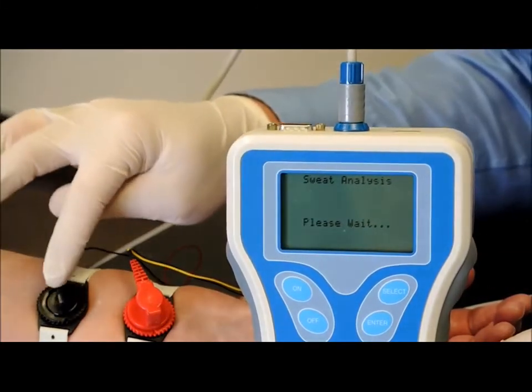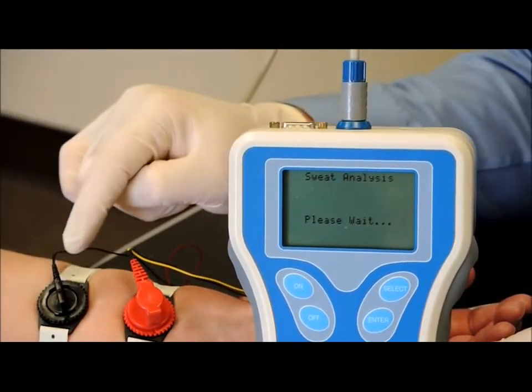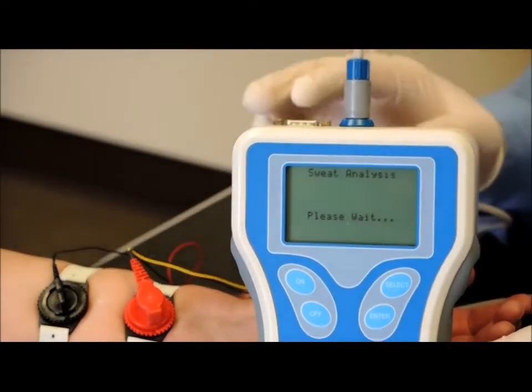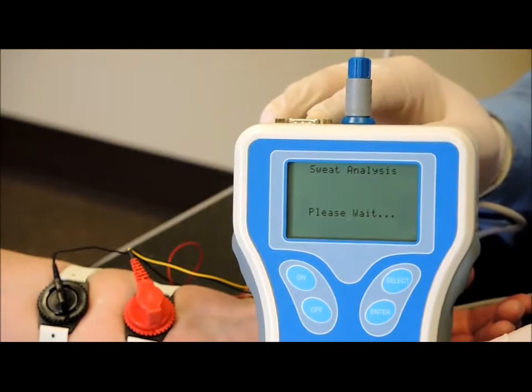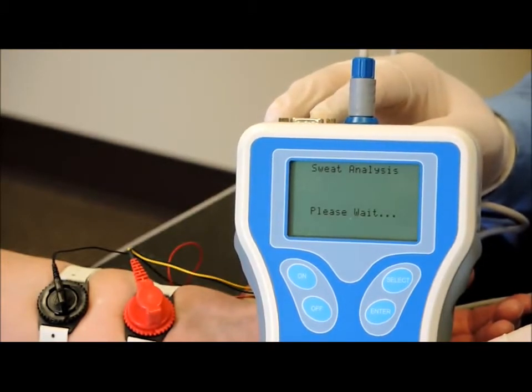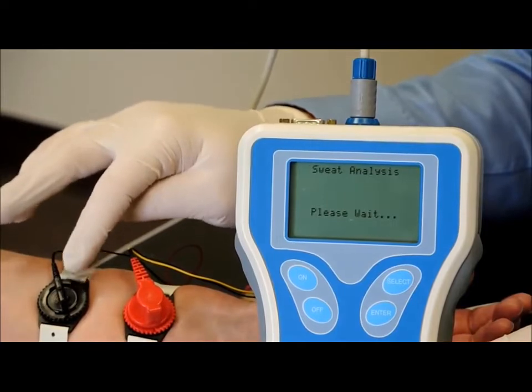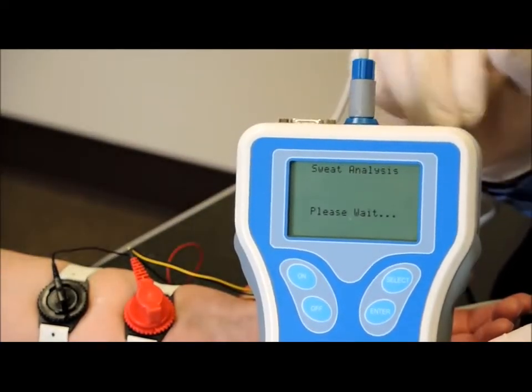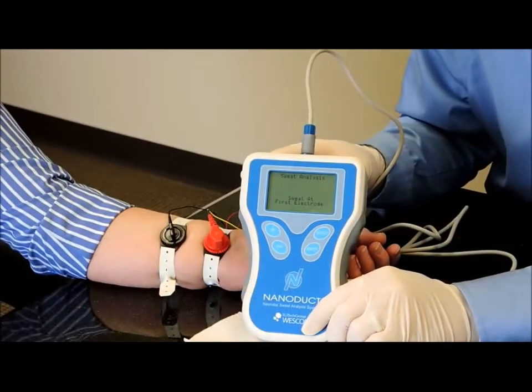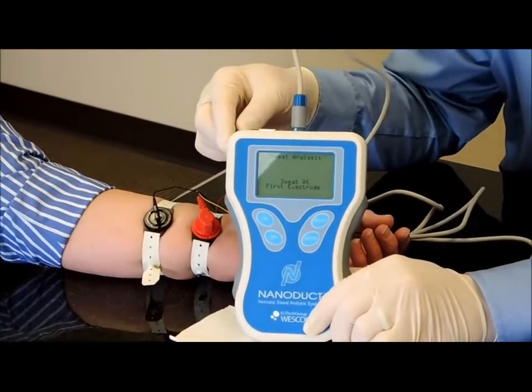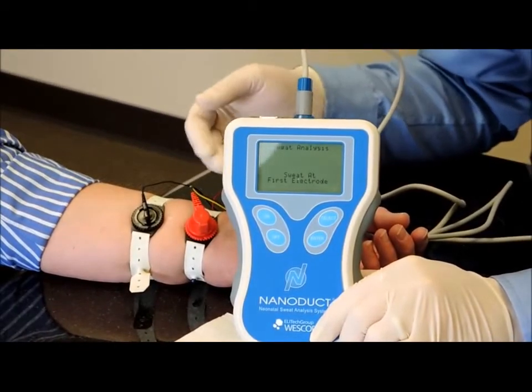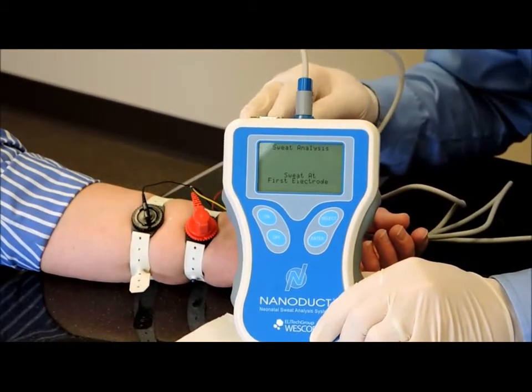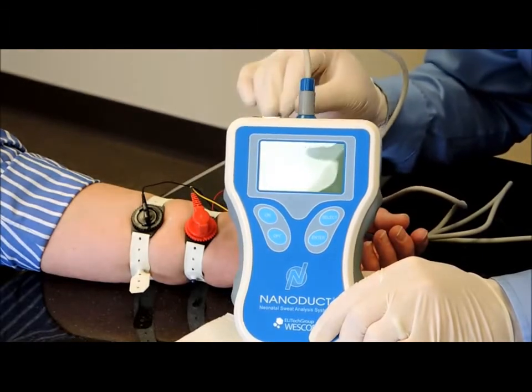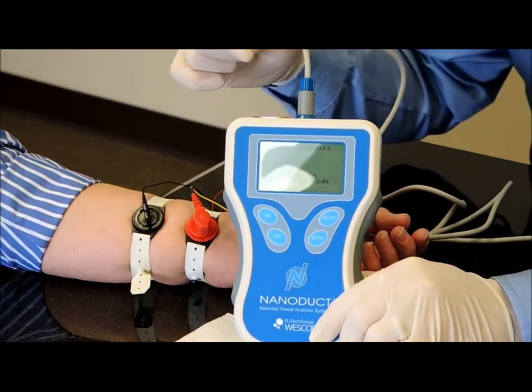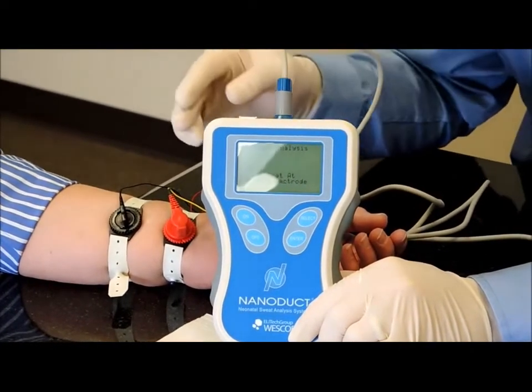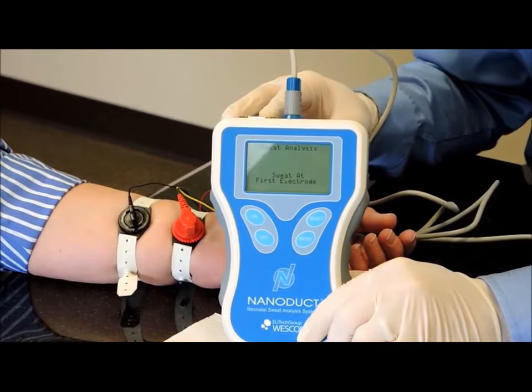Now keep in mind we left the black electrode on the skin. If we had removed that, we would not see that sweat at first electrode, and we would not see a sweating rate. And so that's very important, to keep the black electrode on the skin so we can see those on the Nanoduct. So now you'll see on the screen it says sweat at first electrode. So the sweat from the patient has gotten to the first electrode in the sensor cell. Now about the same amount of time it took to get that reading, we'll see the screen change and we'll start seeing readings displayed on the screen.